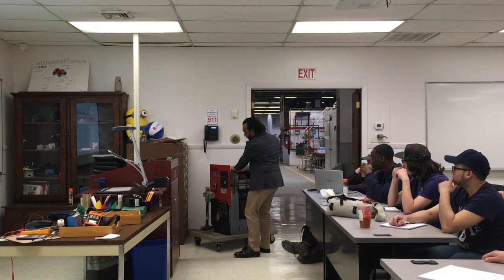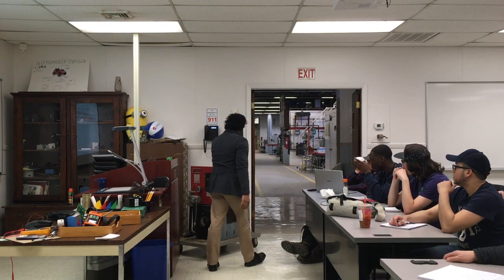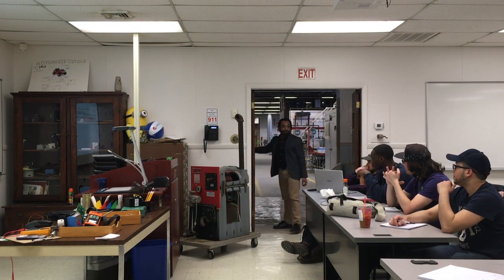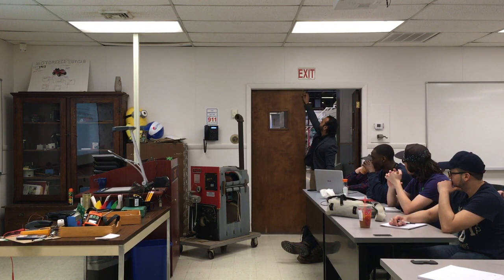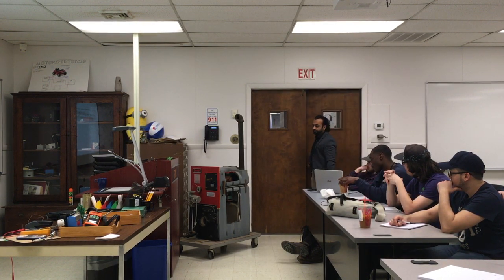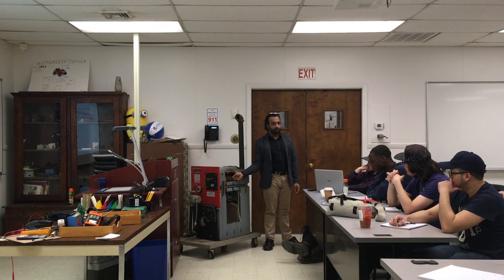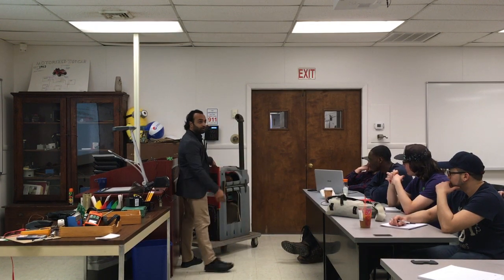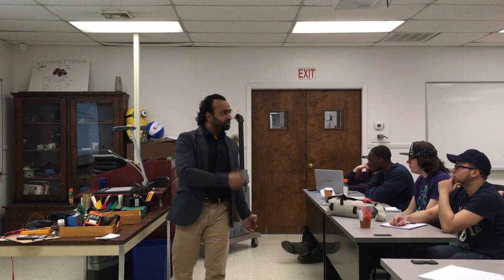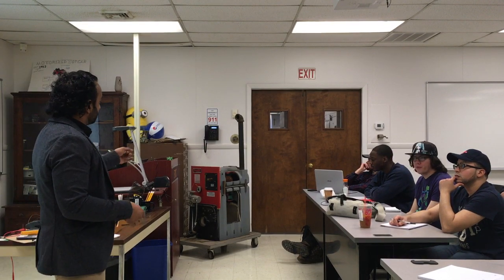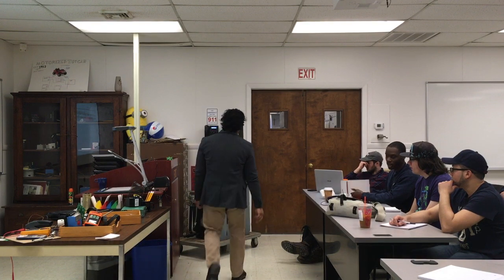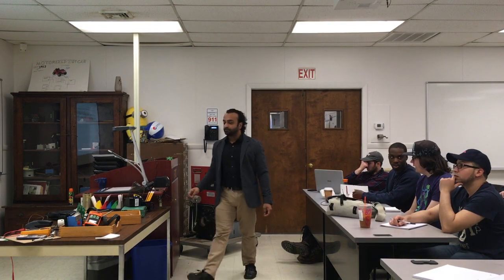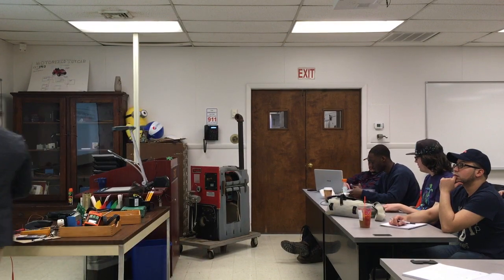This is a steam boiler, it could be hot water. And this will be your coil without a tank. Whenever you turn on the hot water faucet, water will come from here and heat right away in this coil. Water comes from this pipe, goes through the hot water, which is around 200 degrees, and heats up right away. So this is tankless, and it's indirect because the water is not mixing. We're not taking water from the boiler. So this is one way to heat water through a coil.